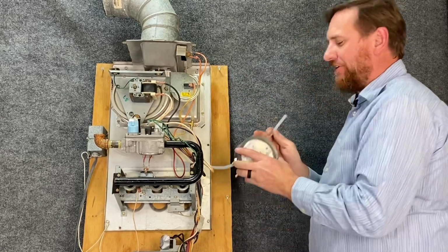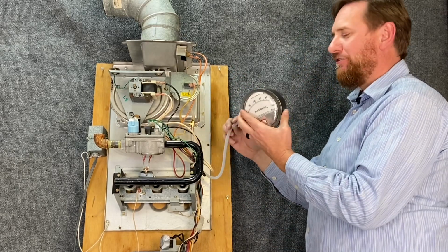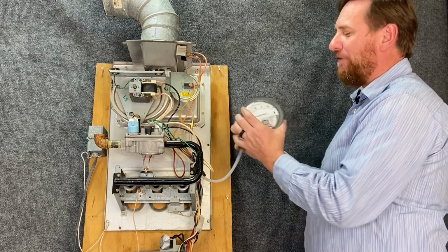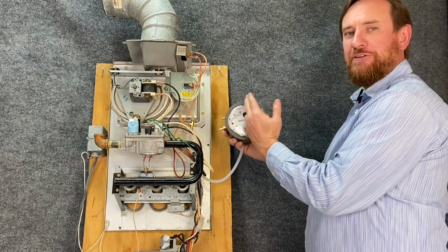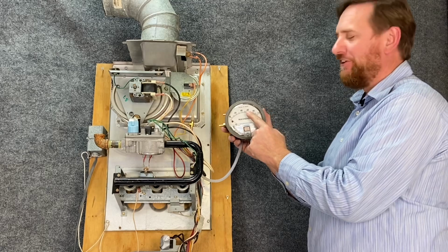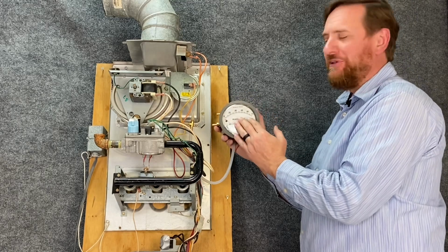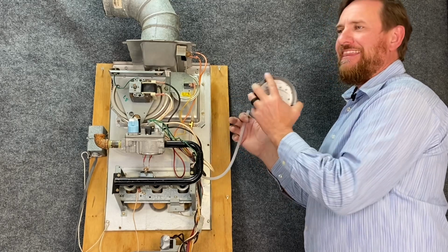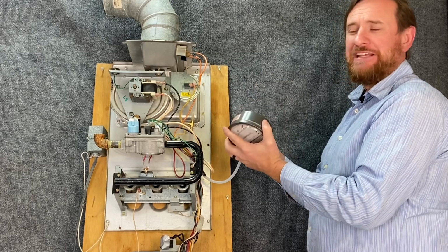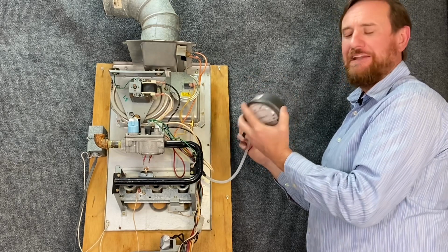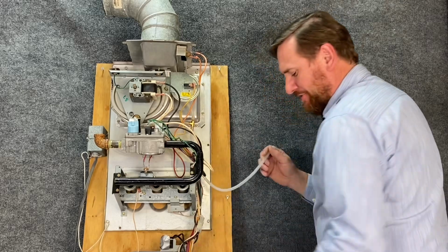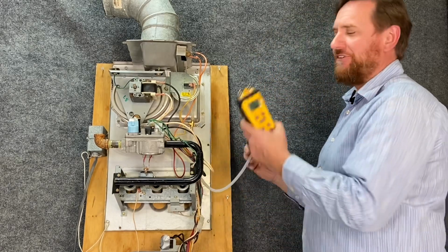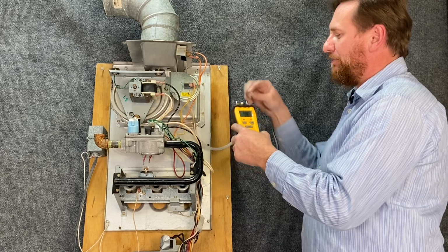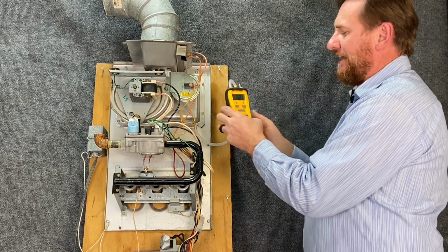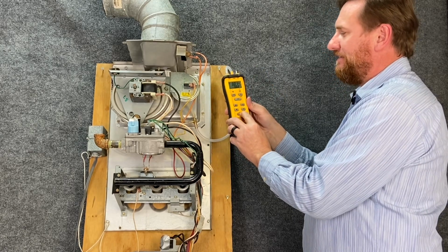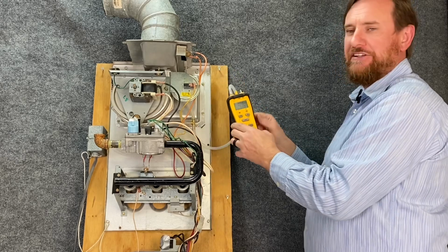In the old days, we used to use a Magnehelic. I would use the low pressure side, and as this ran, I could see how much of a vacuum it's pulling in inches of water column on this tool. The problem with this tool is, over time, they get out of calibration, you have to have them recalibrated, and they bounce around in the truck, which makes them inaccurate. So now we have digital manometers. This is the way to go now. We simply plug this in, and if I want to calibrate it, I just press the 0 button, it zeroes it out, and I'm ready to start.